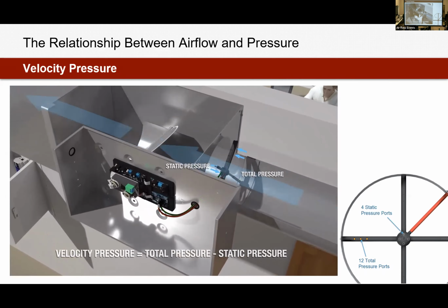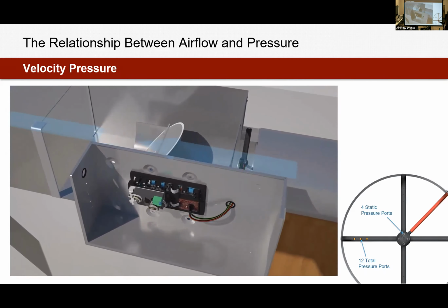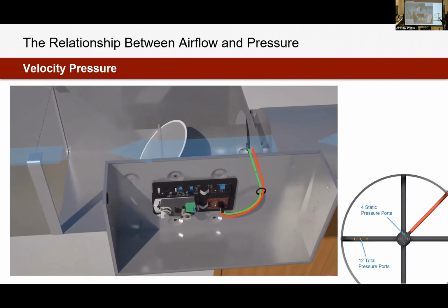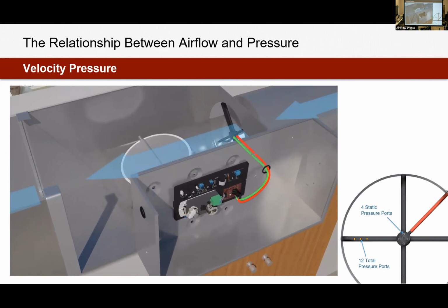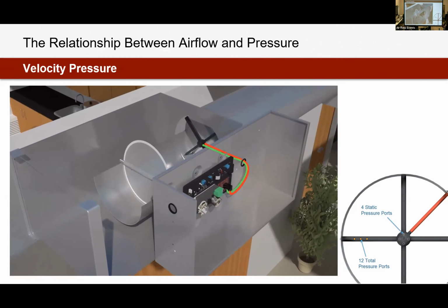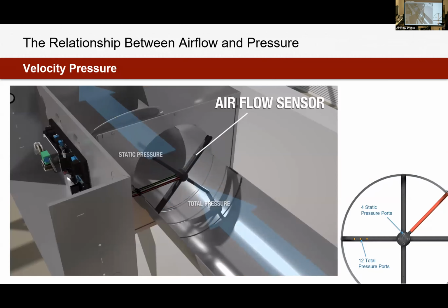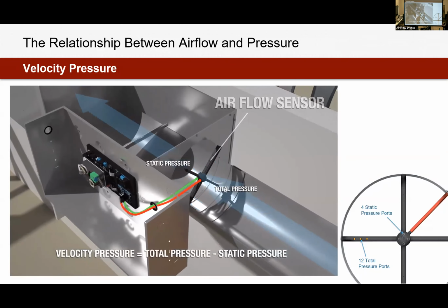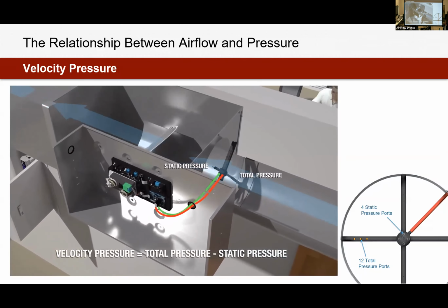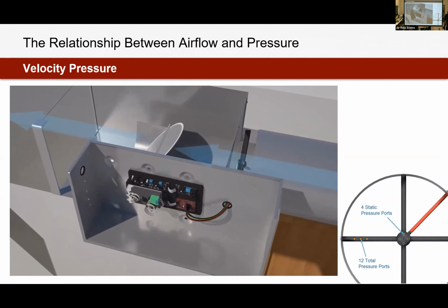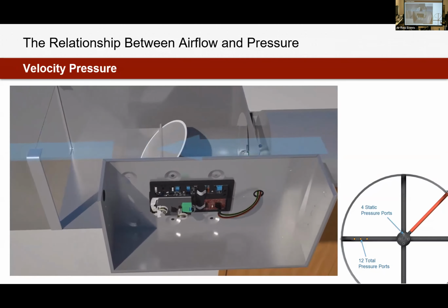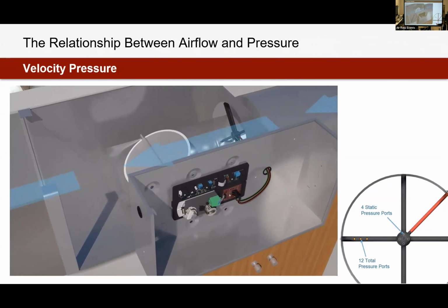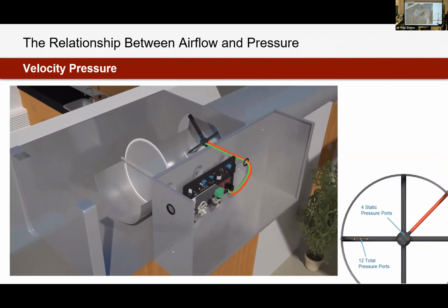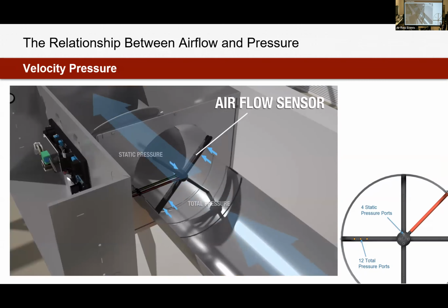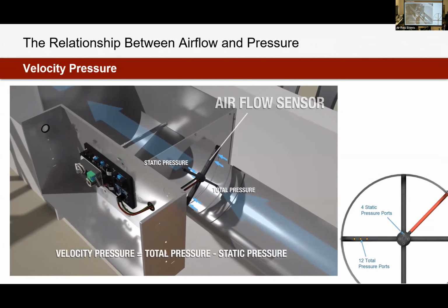velocities into the duct. So something like this, which is called a cross flow sensor, when that image spins around, you can see the inlet a little better. We're mounted to the outside of the duct, but really all of our measuring is happening in the cross there in the middle. On the front face of the sensor, you're picking up total pressure. So again, total pressure, static plus velocity. We're capturing all of the pressure going into the inlet valve.